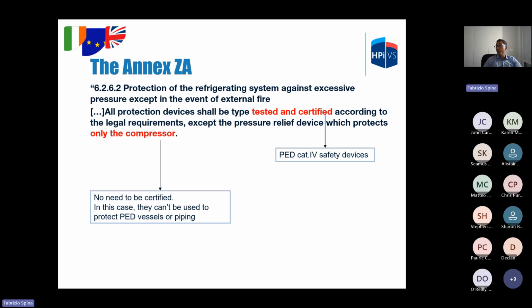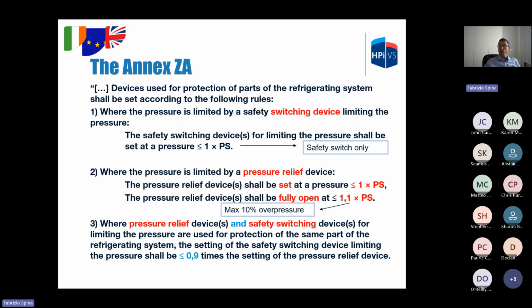Protection of refrigerating systems against excessive pressure. All protection devices shall be type tested and certified. That means that they must be PED certified as category 4 safety devices. The exception is for devices that protect only the compressor. That means that this device can be not certified, but in this case, it cannot be used to protect a PED vessel or piping. So when we have a compressor provided with PRVs that protect only the compressor, it cannot be used to protect the condenser or the oil separator. You need to install a certified PED category 4 device.